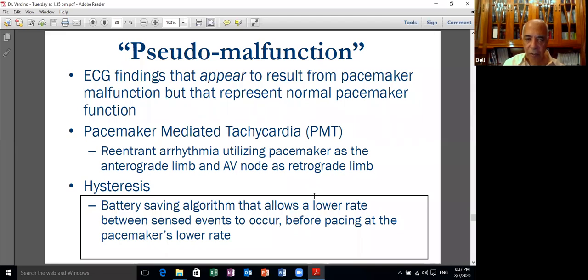Now, hysteresis is a method of saving the battery life. Under these circumstances, if the patient's lower rate limit is set, for example, at 40, then he starts to pace at less than 40, say 39, but when it paces, it paces at a higher rate like 60. Sometimes in patients with carotid sinus syncope or vasodepressor syncope, we pace these patients with the cardioinhibitory component, and we pace at a rate of 100 until the patient regains consciousness, and then we fall back to the lower pacing rate.